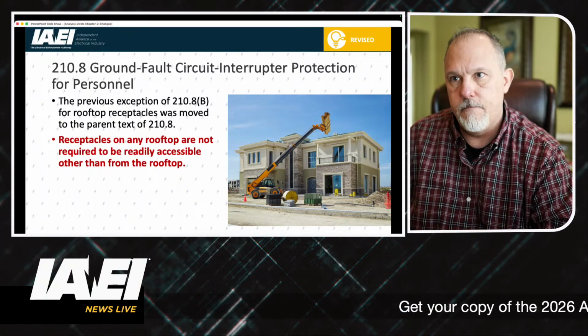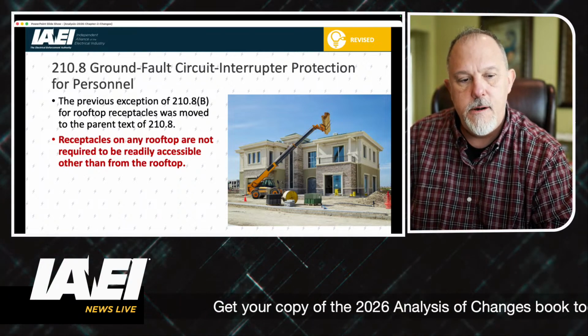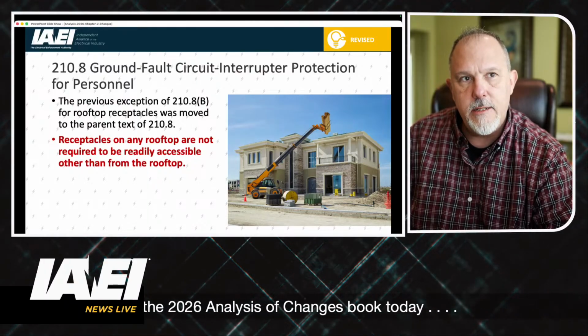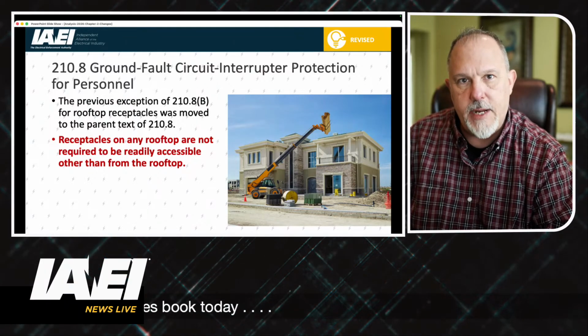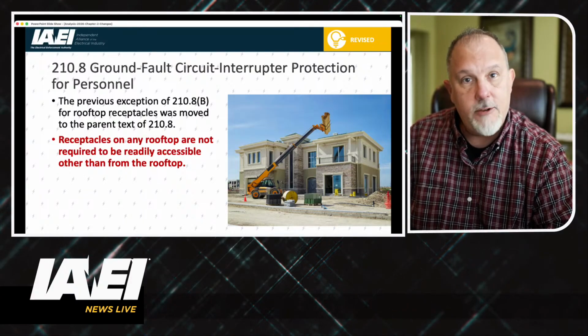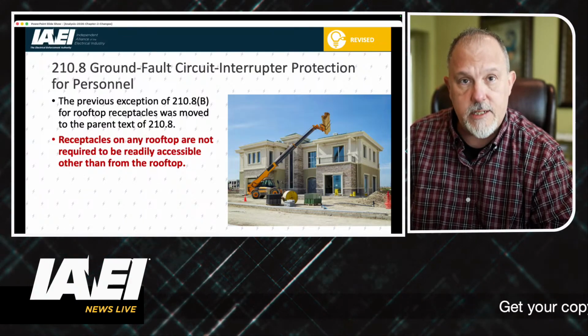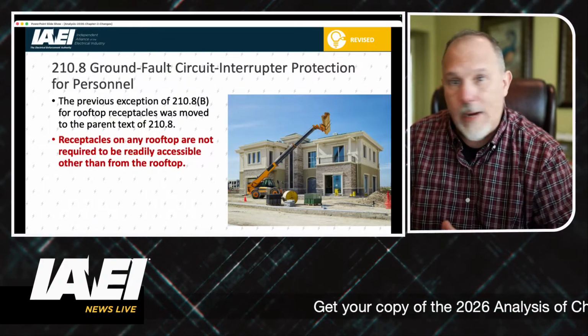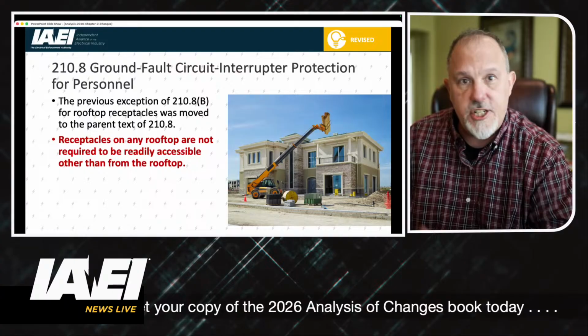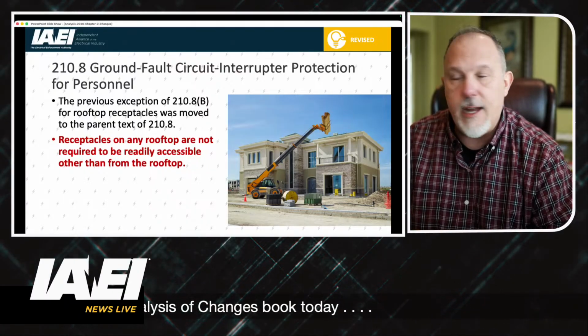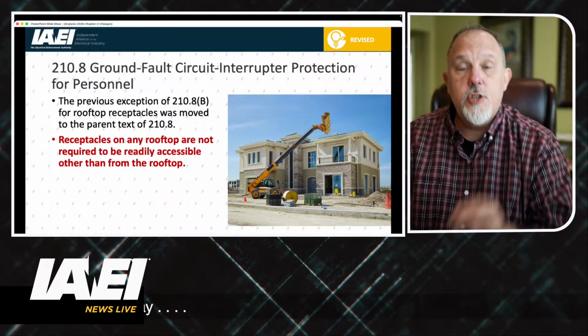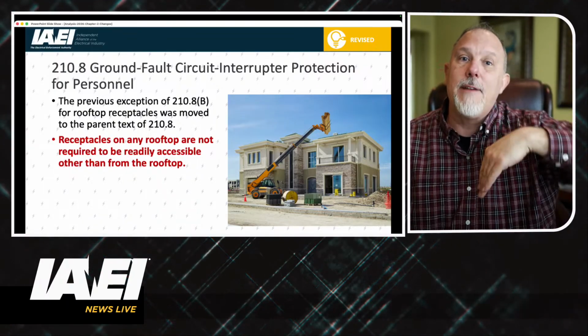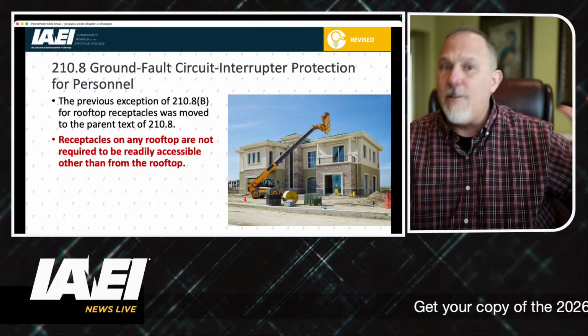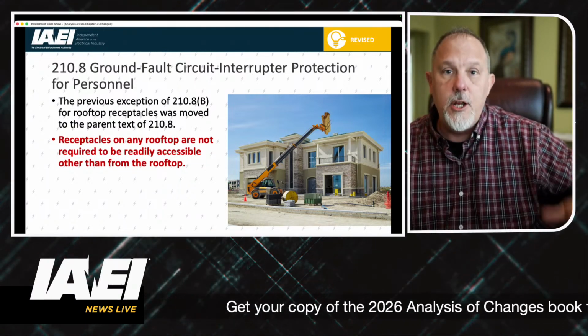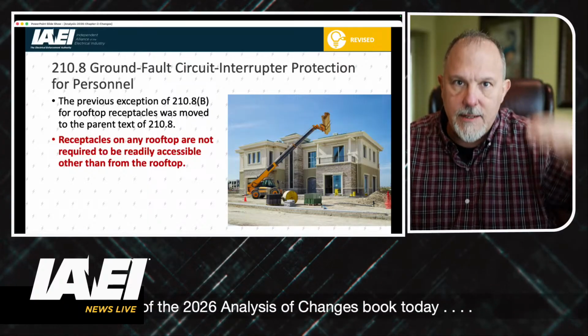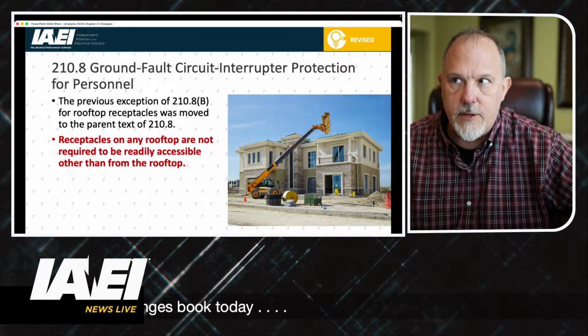So we realized it's not room dependent, but system dependent. I don't care where you have that security system or fire alarm system, I don't care where it's at - we just don't want it on a GFCI or an AFCI, or in this case a GFCI, 210.8 exception. So we moved the exceptions to the parent language, saying it doesn't matter where you're at. This is an exception not to an area, but to the entire section of 210.8.